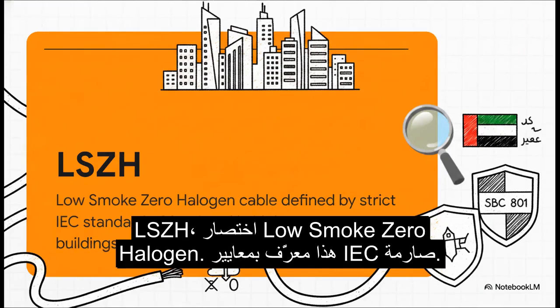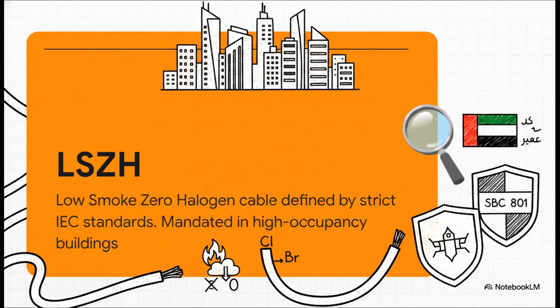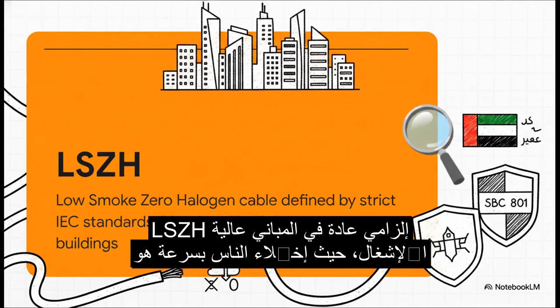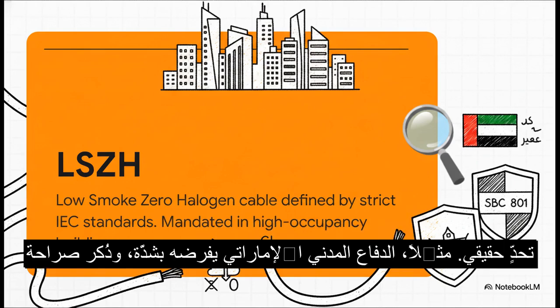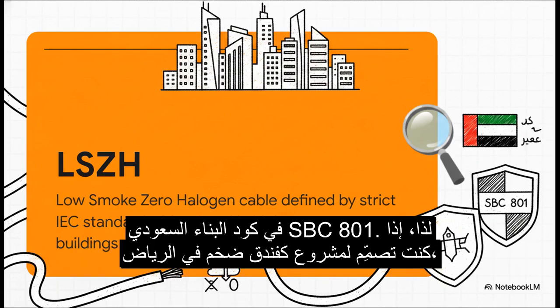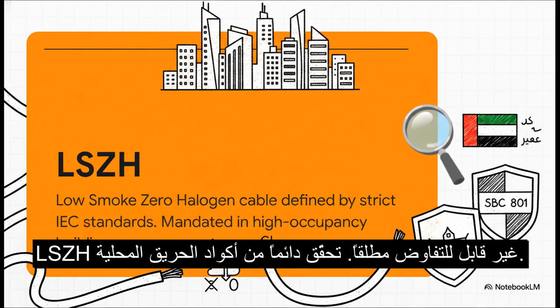And finally, LSZH, which stands for Low Smoke Zero Halogen. This one is defined by strict IEC standards. LSZH is commonly mandated in high-occupancy buildings where evacuating people quickly is a real challenge. For example, it's heavily mandated by UAE Civil Defense and explicitly referenced in Saudi SBC 801. So, if you're designing for a project like a massive hotel in Riyadh, LSZH is absolutely non-negotiable. Always check your local fire codes.